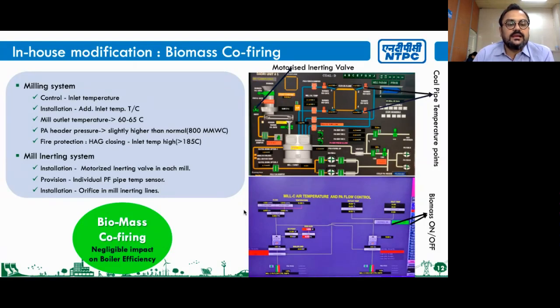So now talking about the mill inerting system changes. In the mill inerting system, we have installed a motorized inerting valve in each mill so that the operator can operate the valve in case of emergency from the control room itself. We have installed individual PF pipe temperature sensors so that fire can be detected beforehand. We have also installed an orifice in each of the mill inerting lines to reduce the steam pressure so that proper blanketing of fire can be done. We have also observed that there is negligible impact on boiler efficiency from biomass co-firing.